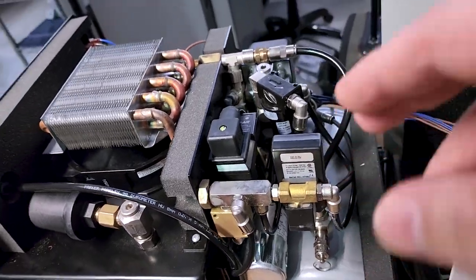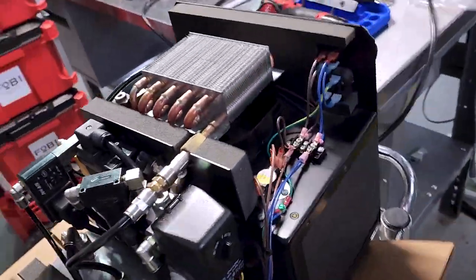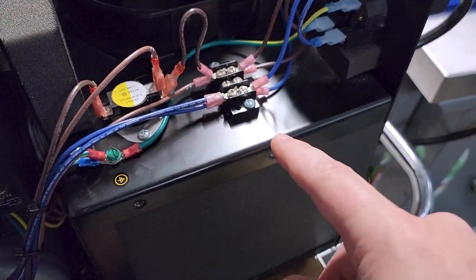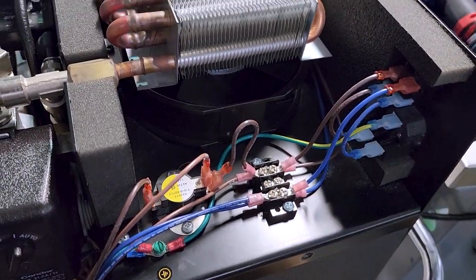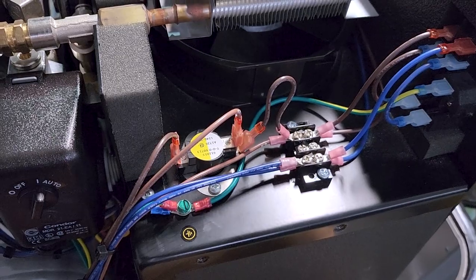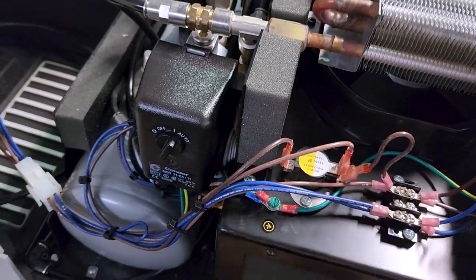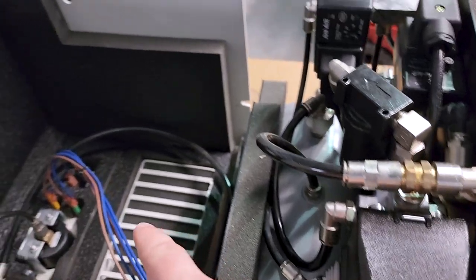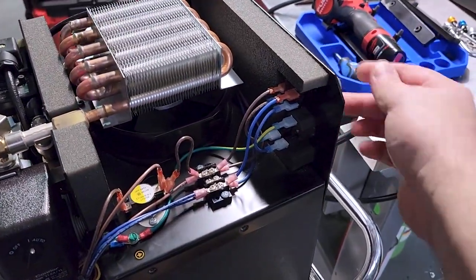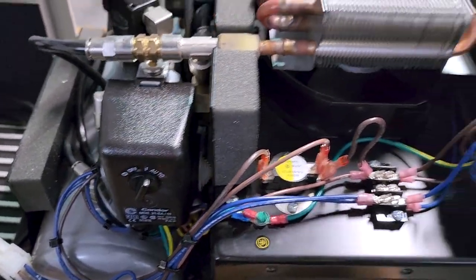So the real layout for this guy, let's go ahead and let's start from the IEC on this side. And it's really nicely laid out. European wiring code. You can see the brown and the blue. Brown is the hot. And an open terminal block right here. So watch yourselves if you guys ever open these guys because it does have exposed connections. You have a temperature switch right here. So this guy here is going to kill it if it gets too hot. And you can see it's all in series. You can see how it comes here. It goes there. It goes there. And that goes down to your control module and to your front control panel. So that would be your status indicators on the front.